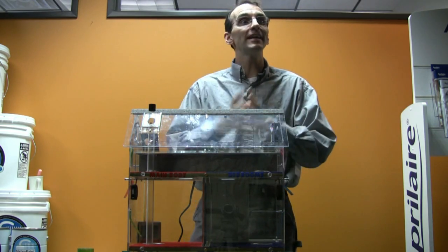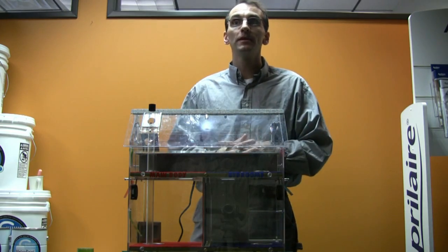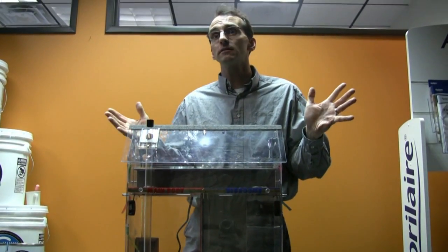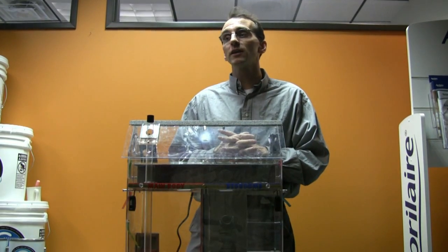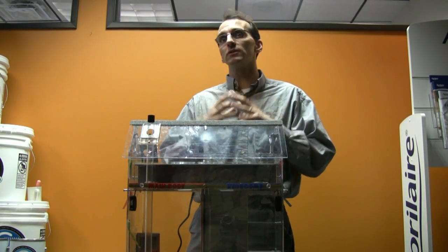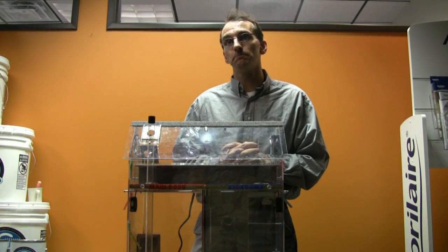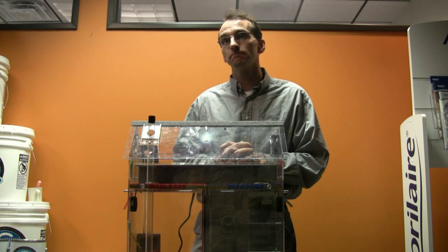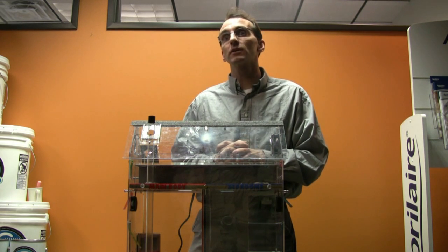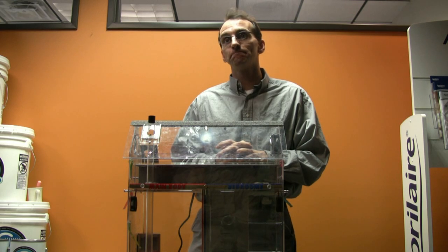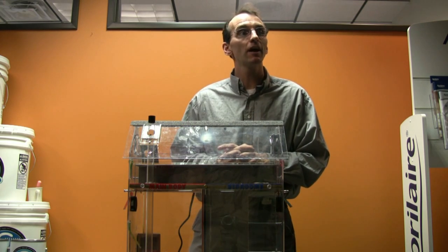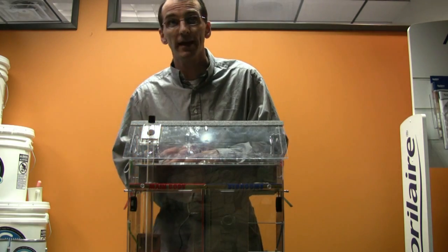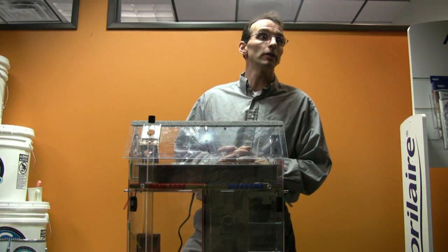Anytime you have a panned-off joist system, you can basically not seal it anyway. You really should be looking into replacing that with an actual ducted system. But aren't most new homes built in the 90s or early, like, stud cavities where most of your cold air returns are? No, they actually have ductwork in the cavities. People haven't used panned-off joist bays. By code, you haven't been able to use a panned-off joist bay since, I don't even know.